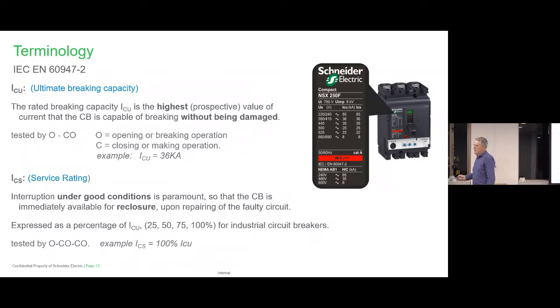Yes, good question. There's more than one answer to it, but I'll give you the bad answer. The answer is, if it has seen this level of fault, it will need to be replaced at the end, because that's a massive amount of fault. If you looked at the circuit breaker, and I've seen plenty of breakers that have seen really massive faults, there is carbon around it. If you open them up, the contacts haven't welded, because ours don't weld. But the damage is there. You can't reuse that anymore. But it's been safe at that time.